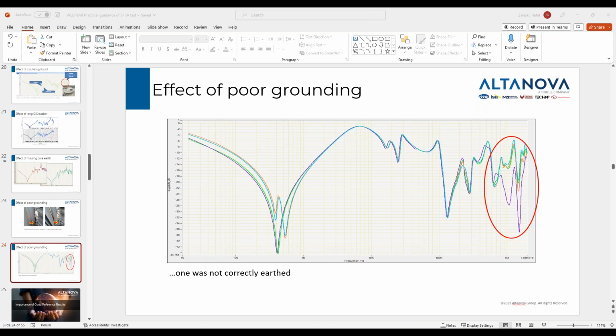If they don't align very well, interpretation needs to be expanded, maybe on the basis of reference results, on the basis of your previous experience to see what could have gone wrong, maybe on the basis of the history of the transformer, and maybe the transformer failed in service and you arrive for this reason. So if they don't align with each other perfectly, it can mean both. And usually the low frequency side differs in a way that outer traces have 2 dips in the trace, and the middle phase has only 1.